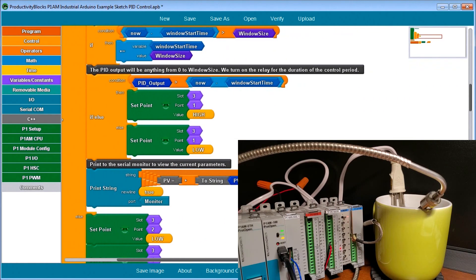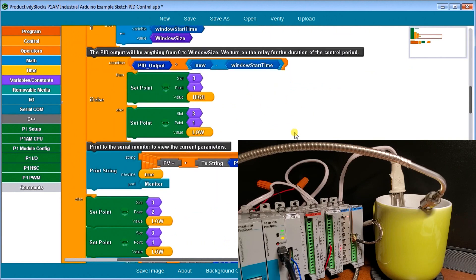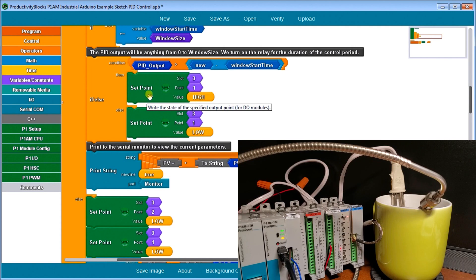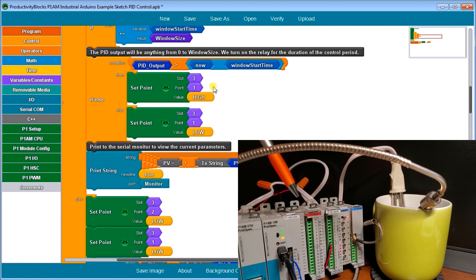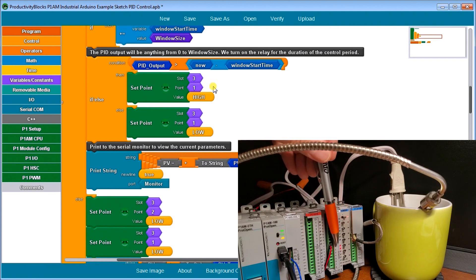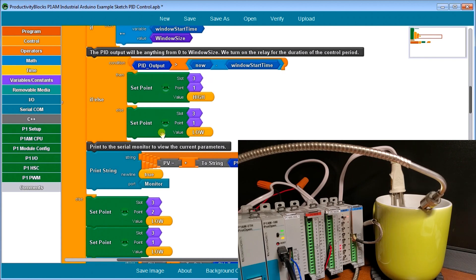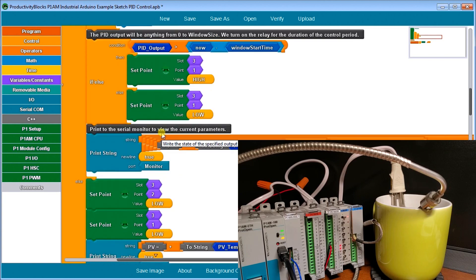Then once the PID, we look at it and we actually will turn it on and off based on the control cycle or that period or the window size. So if our PID output is greater than the window now minus the window start time, then we turn on our output relay, which is the third slot first channel. So it will actually oscillate that output relay to control our temperature. If it's not on, then we turn it off. So that's basically our PID loop.